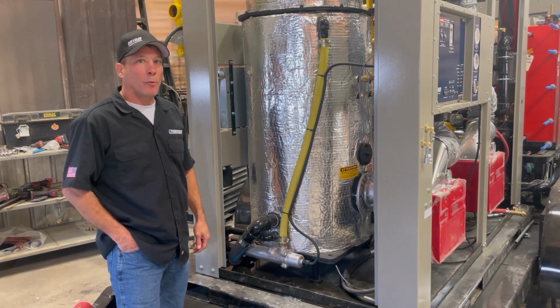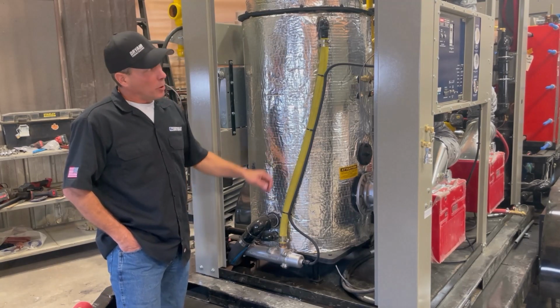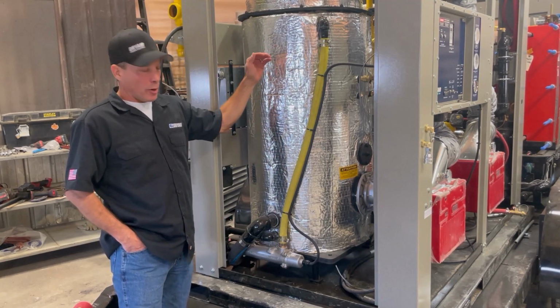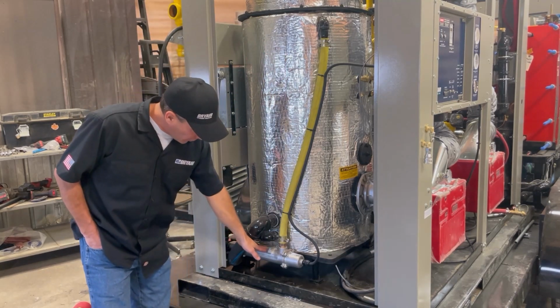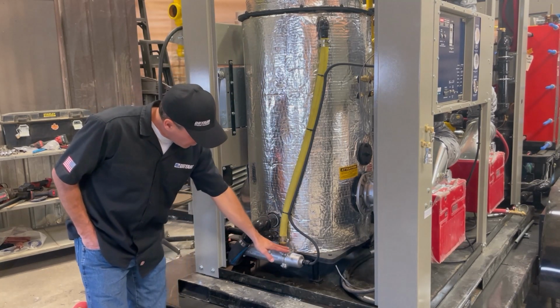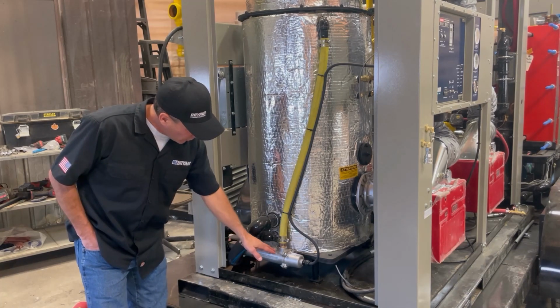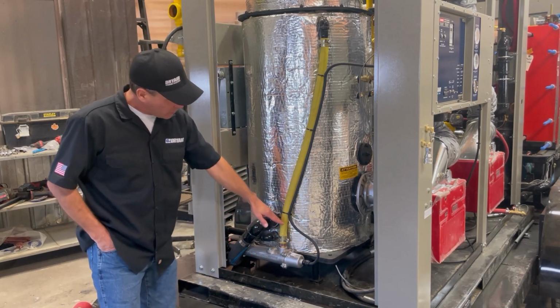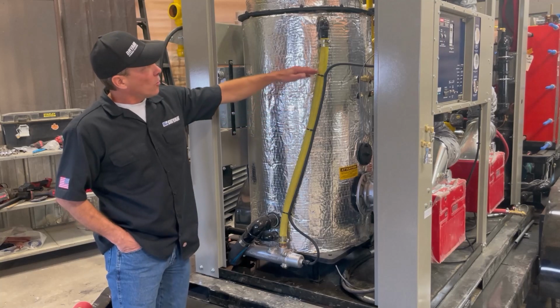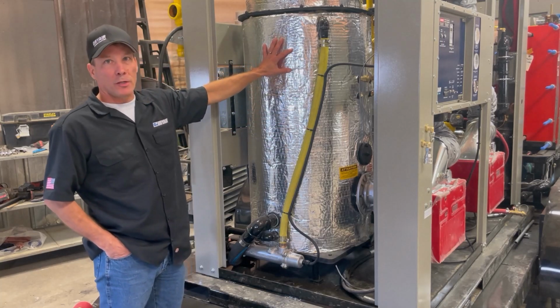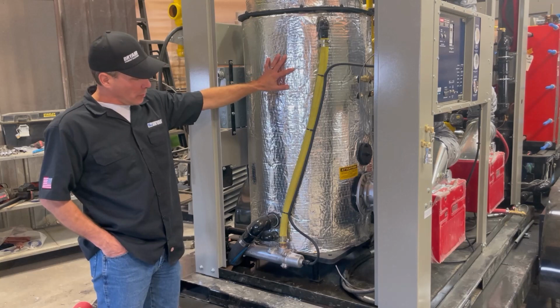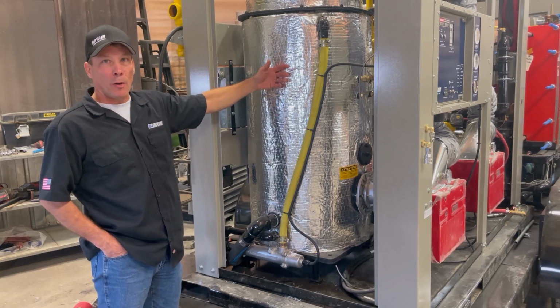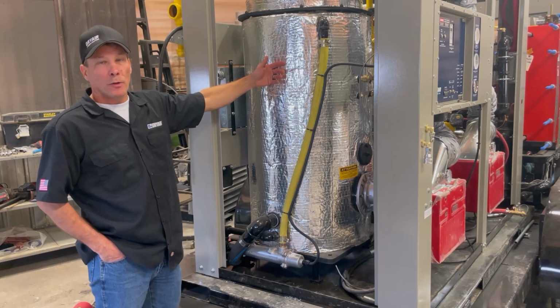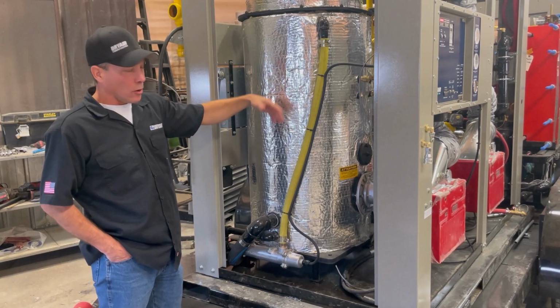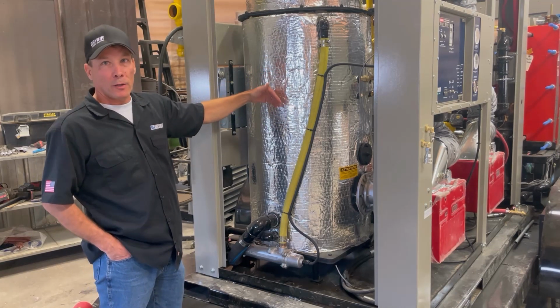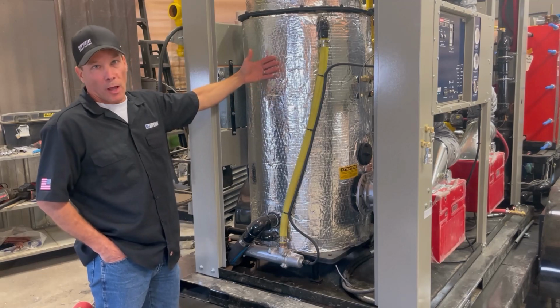So we're going to talk about the preheater on the unit. When you plug the unit in, you have power to it, you turn your breakers on. You have this preheater here that will heat up. It is full of glycol, and what it does, it heats the glycol, and as it gets warmer, this will all heat, and it helps heat the glycol in the exchanger. We do that so when you turn your pump on and you hit the burner, then you have hot glycol going through your pump, and it starts a lot better.